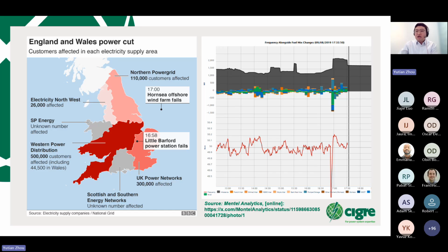And then very shortly after that, the steam unit at Little Barford Power Station in Bedfordshire, which is rated at 244 megawatts, disconnected from the transmission system. The speed sensors on the steam turbine produced a discrepancy, basically, and initiated its automated control system to shut down. So this so far has led to a total loss of power generation of more than 1.1 gigawatts within just 1 second of the fault.